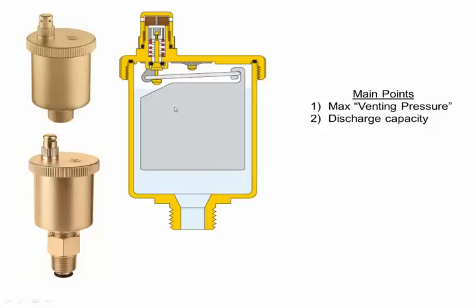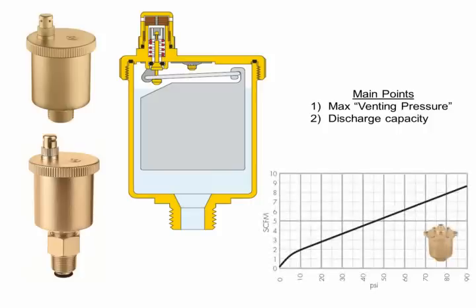Now, the two things to remember about air vents: maximum venting pressure, that's the pressure at which the air vent will cease working, because the pressure times the area on the bottom of this pin indicates the upward force. If that gets higher than the weight of the float, then regardless of how much air gets built up here, you won't vent air. And air vents are rated from anywhere from 35 psi to 120 or something like that, so just keep that in mind.